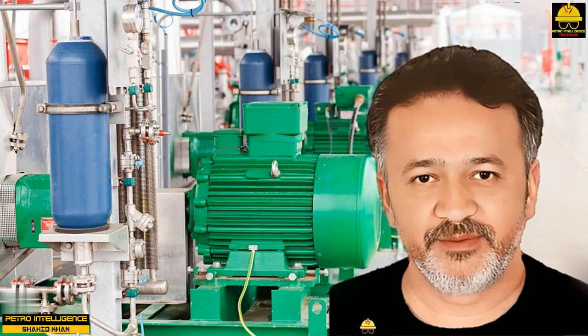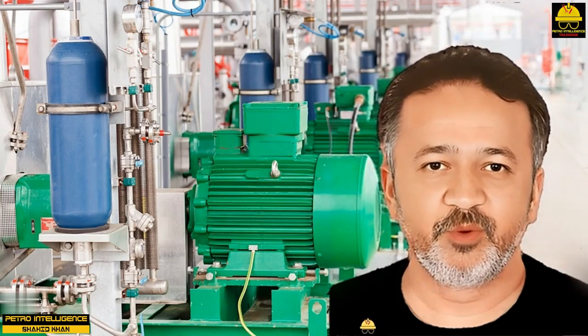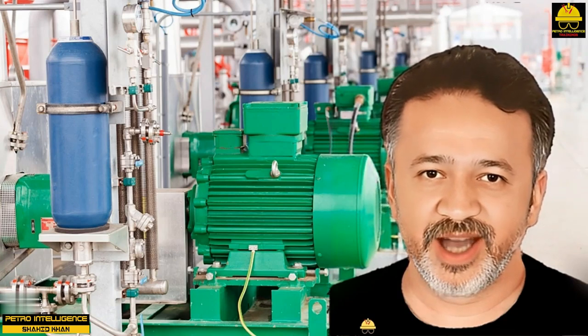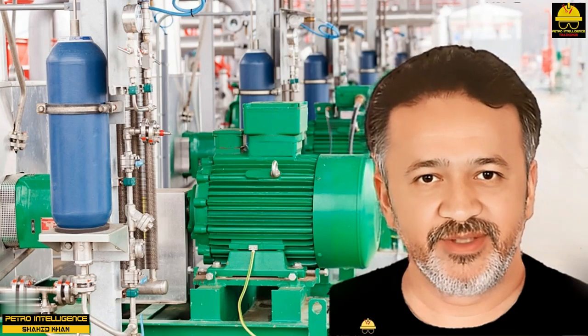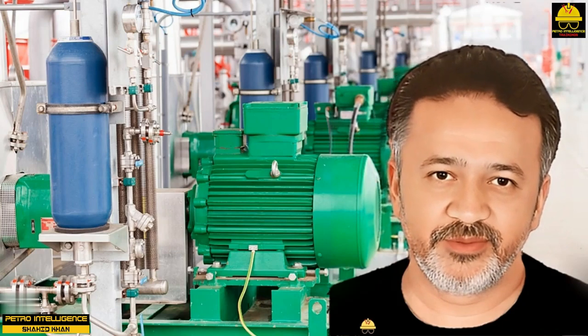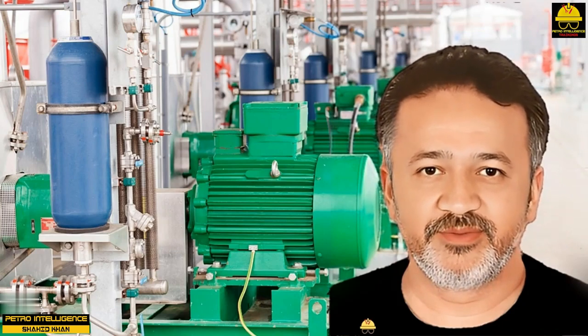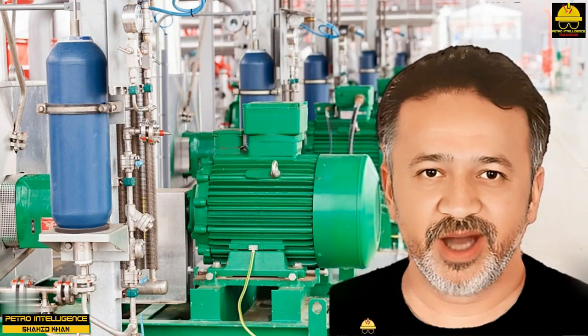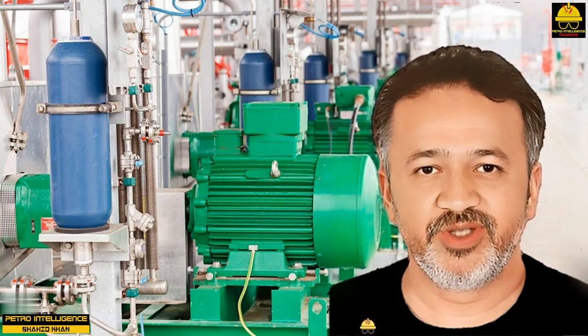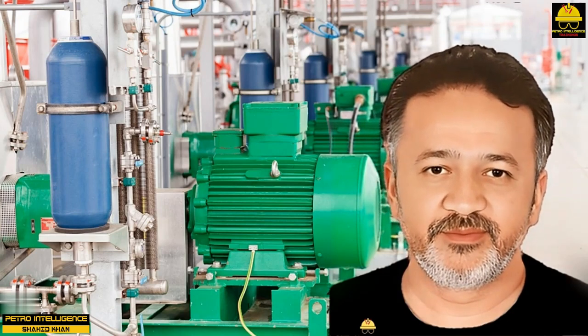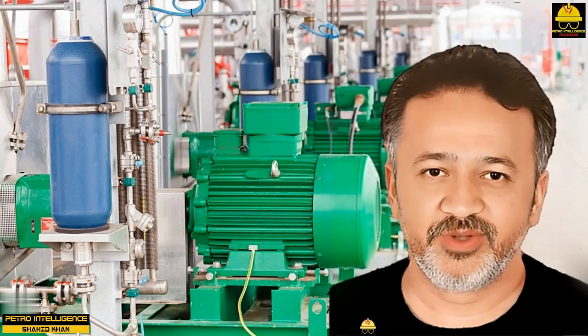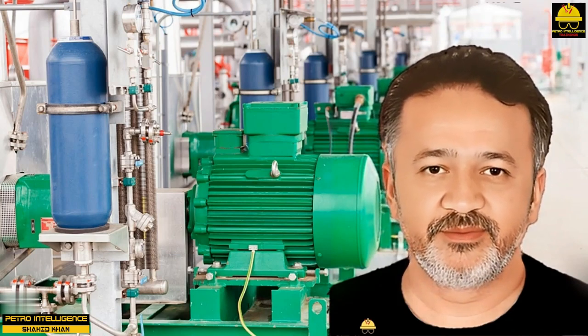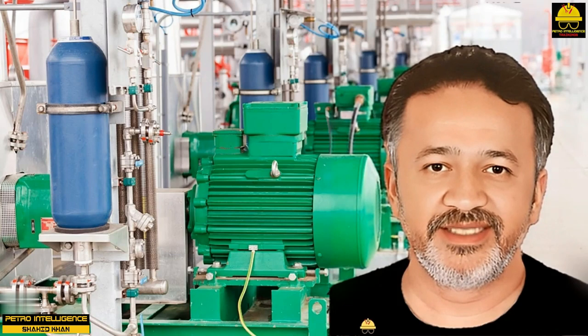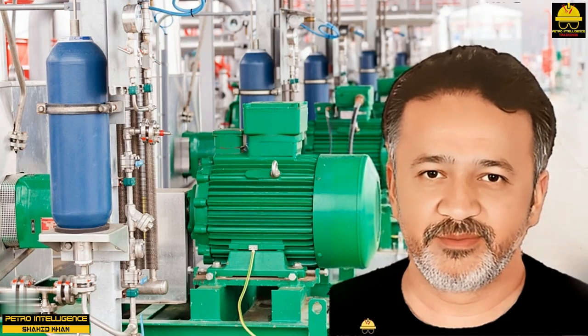There are two ways to minimize thrust. One way is to use a balance device, a hydraulic system that connects the pump suction to the discharge end of the pump. The system is composed of a discharge side balancing drum, a balance line, and a low-pressure reservoir behind the drum. Another way is to align the impellers in opposite directions. Opposite alignment maintains even thrust along the shaft.